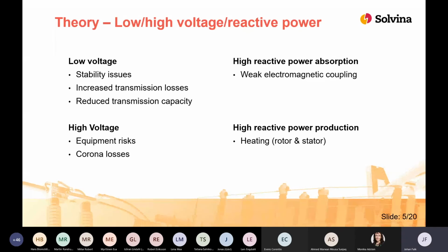So, why should we care about voltage control and reactive power in the region? Regarding voltage, if the voltage gets too low, we might have stability issues. This is especially true during stressed conditions. And in the worst case, we might have propagating outages. Low voltage may also affect the transmission losses and affect the transmission capacity. High voltage might be negative for equipment.